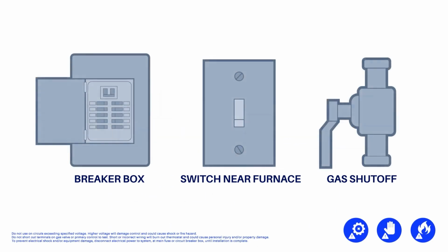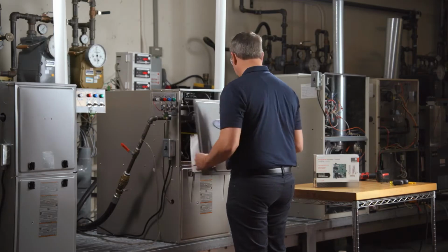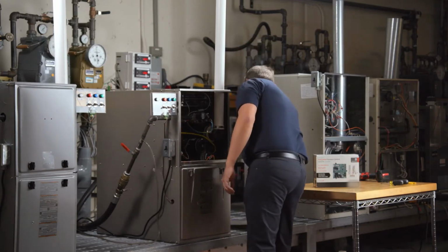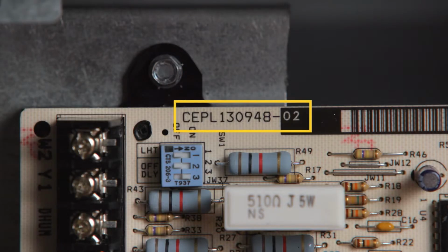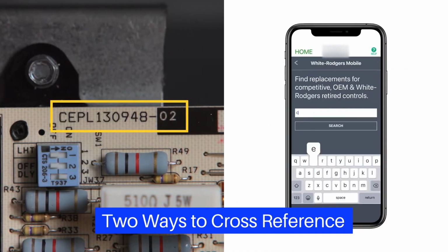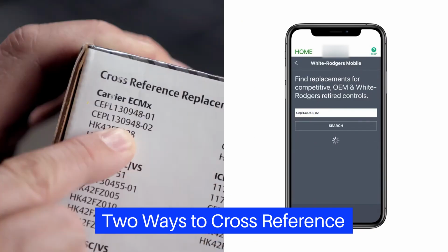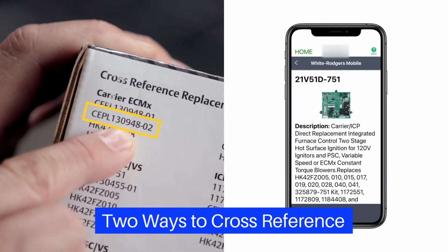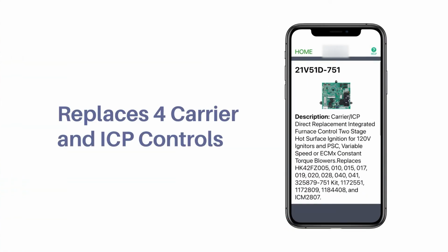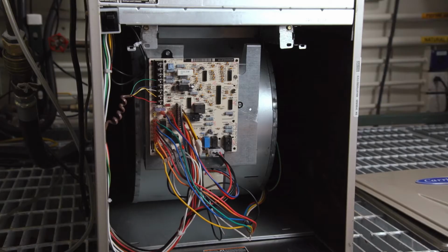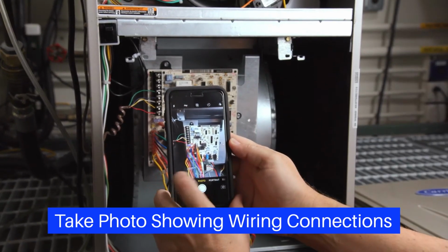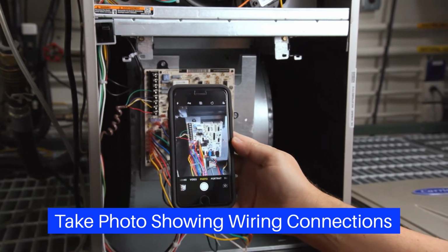First, ensure power and gas are disconnected prior to servicing the furnace. Remove the unit access panels. Check the part number on the existing control and verify it can be replaced with the 21V51D-751 using the cross-reference on the side of the carton or the White-Rodgers mobile app. This control replaces 4 Carrier ICP controls. Take a picture of the existing control for reference before disconnecting wires.